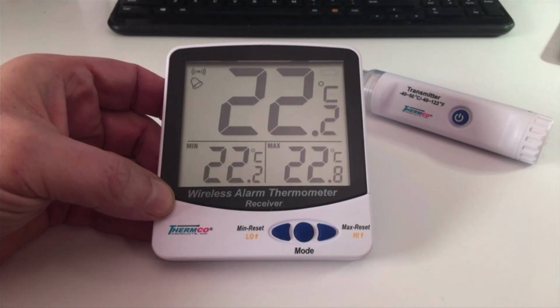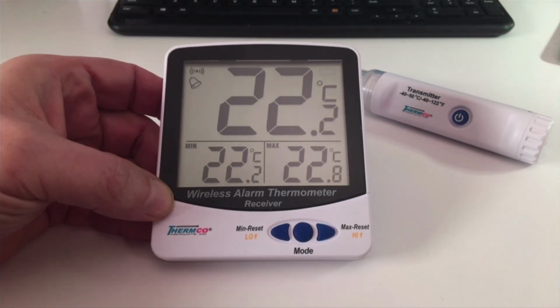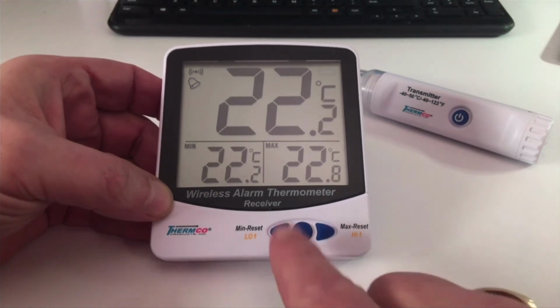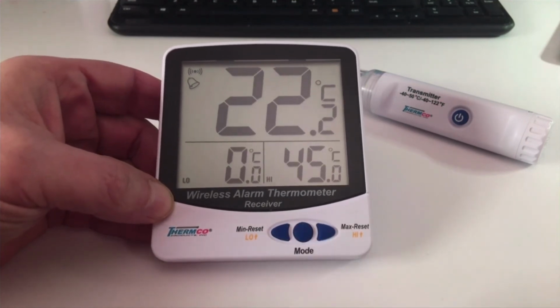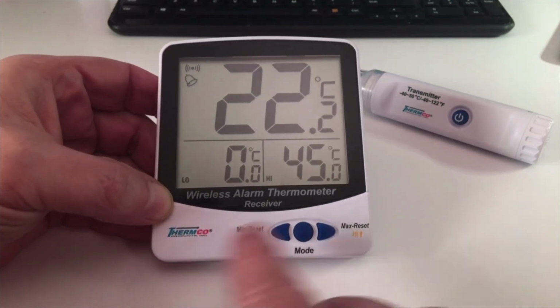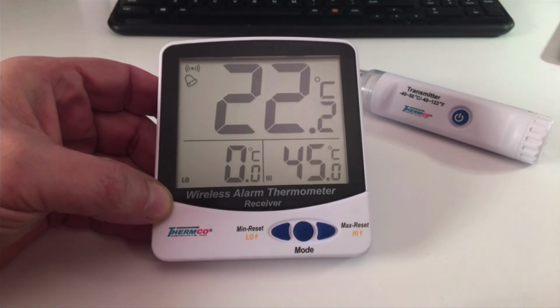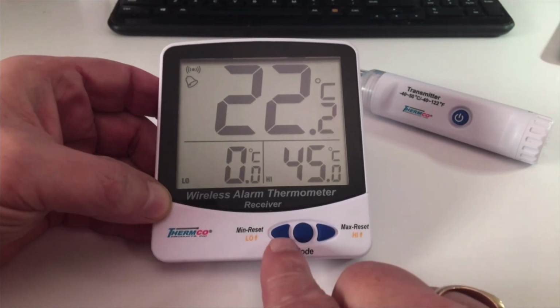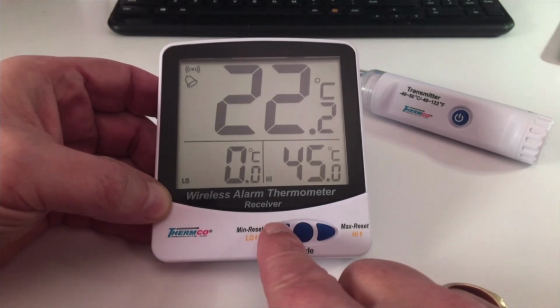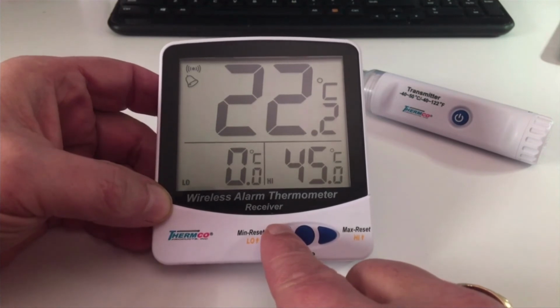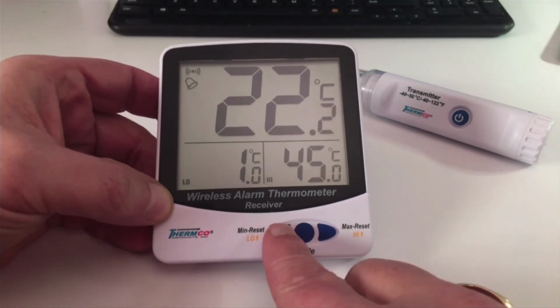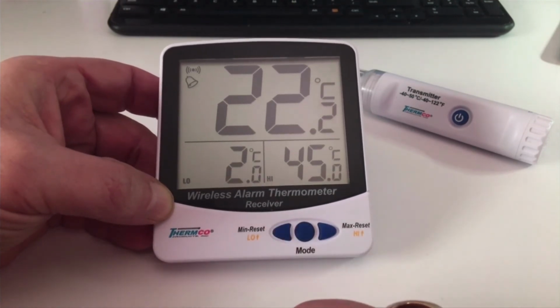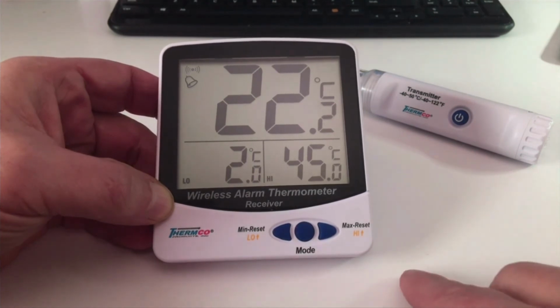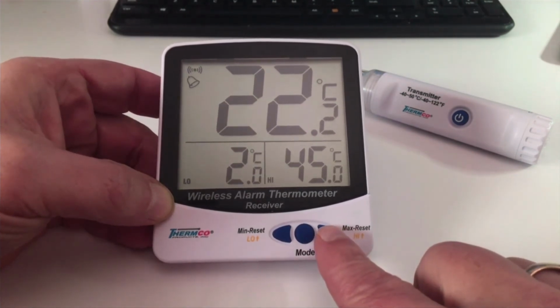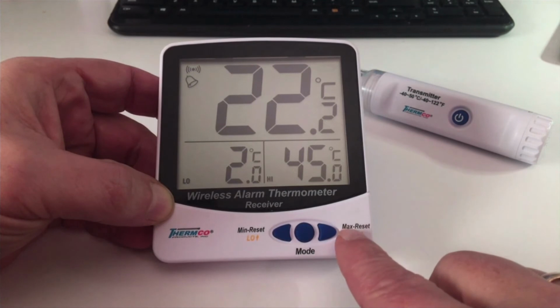Okay, now that we're receiving temperatures from our wireless probe, let's set our alarms. Press the mode button, and the display will change to low and high in the lower section. The button marked low will set our low alarm setting. I want 2 degrees, so I'll just hit this 2 times. And I want a high alarm of 8 degrees. So I am past 8 degrees.